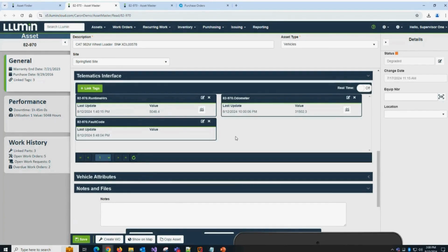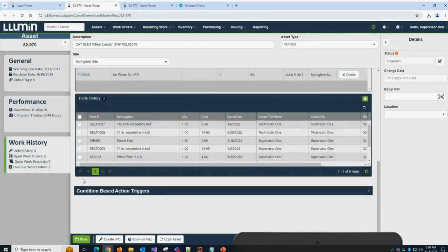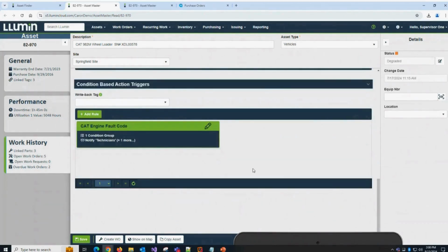But in addition to just triggering those routine PMs automatically, you can also set up more proactive and even predictive condition-based rules to monitor for situations where the equipment is starting to operate out of spec or experience a problem, and have the system automatically alert you and take additional actions so you can proactively deal with those problems before they become a bigger issue or even a downtime event.